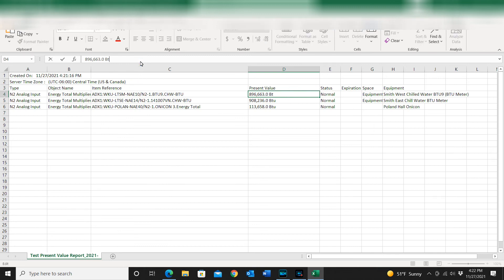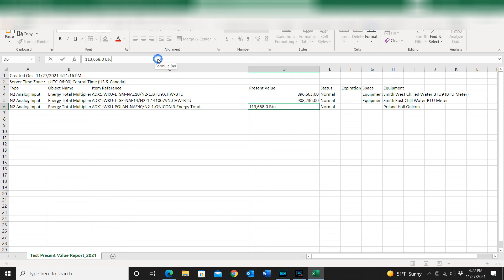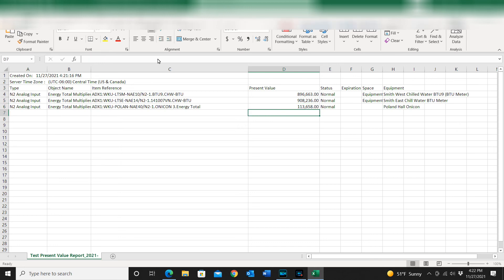If the goal is keeping it simple, go into Metasys and remove the state text on those points — as you can see it doesn't take long to delete them. If this is a report you'll be running regularly I'd highly suggest going in and setting your state text to nothing so it automatically populates in Excel as a numeric value ready for calculations. That's exactly what I did for our utility reports — removed the state text to get pure numbers we can manipulate for billing calculations.